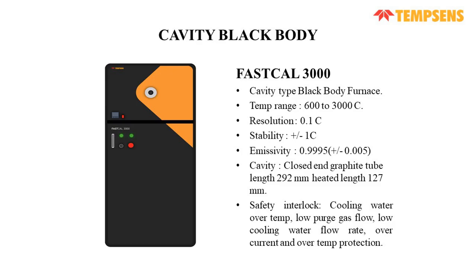Next we have FastCal 3000. It has a temperature range of 600 to 3000 with a resolution of 0.1 and stability of plus minus 1 degree. Emissivity is 0.9995, and it is also a cavity based black body, and it comes with a chiller unit as well as several safety interlocks.